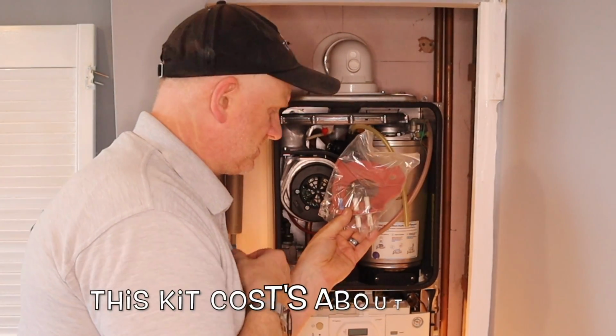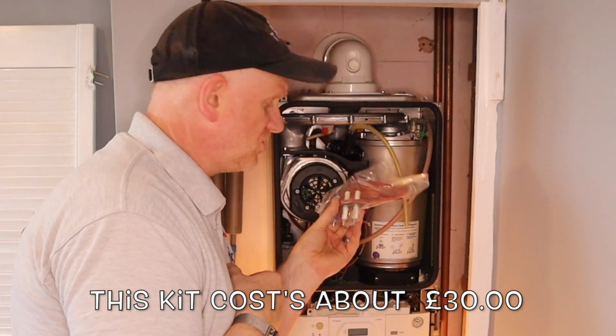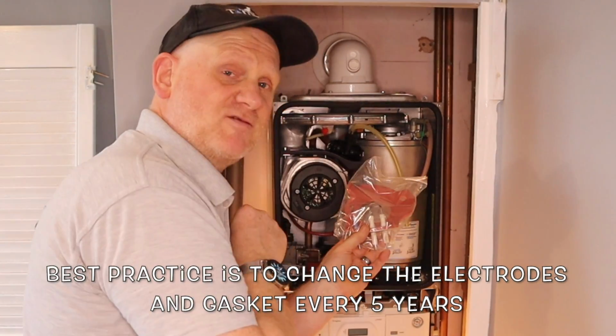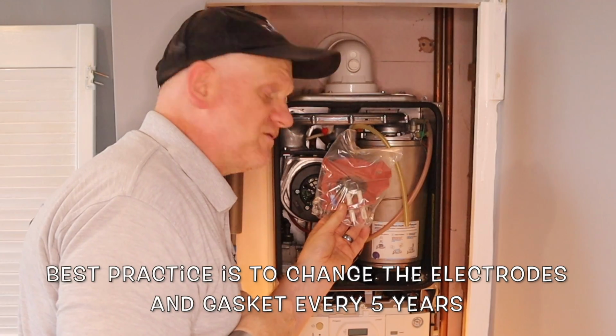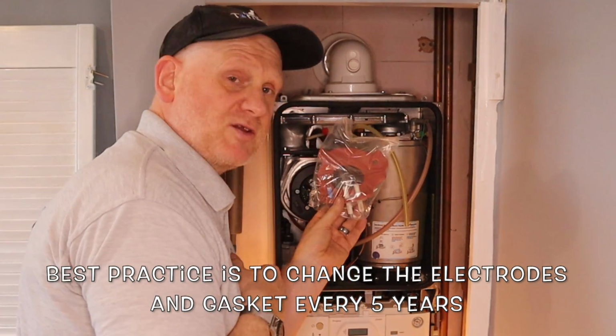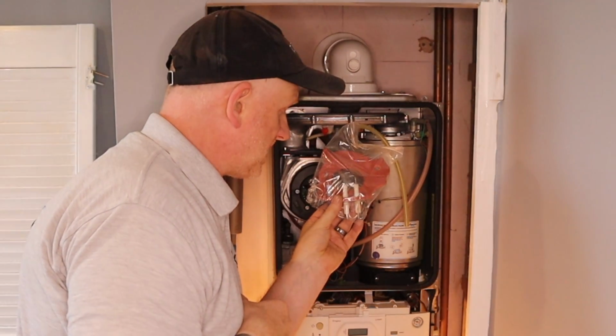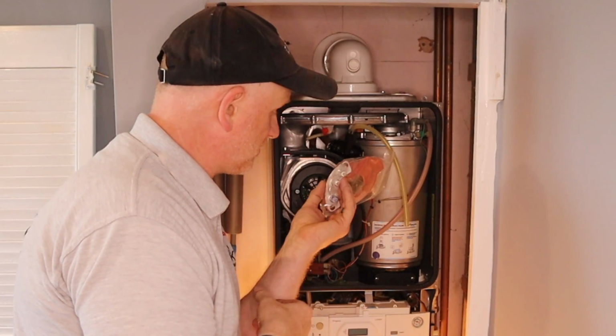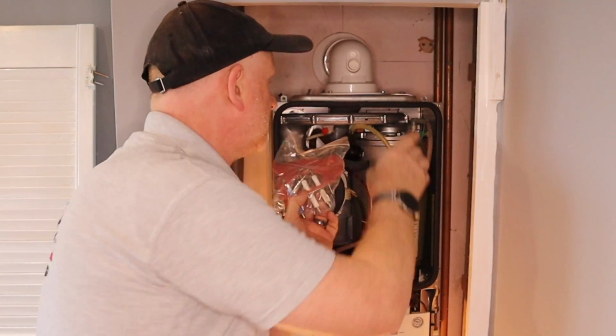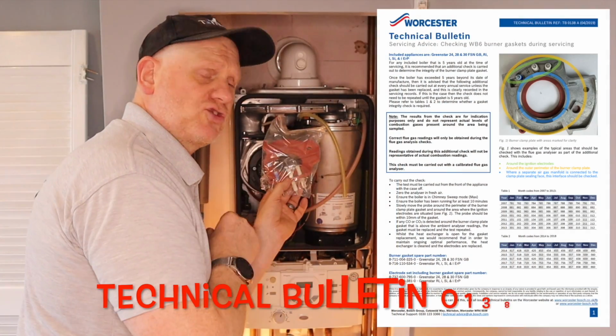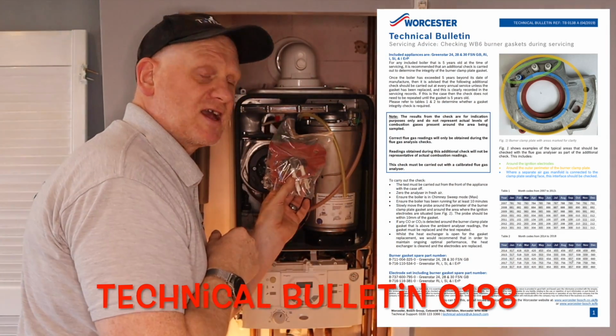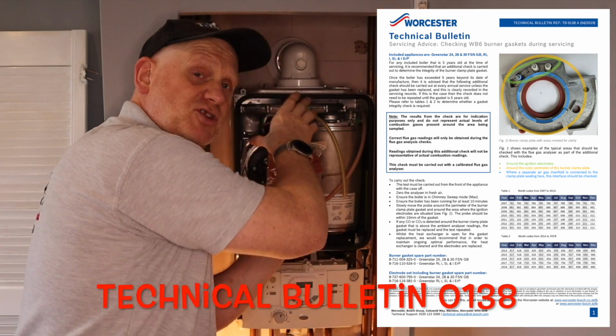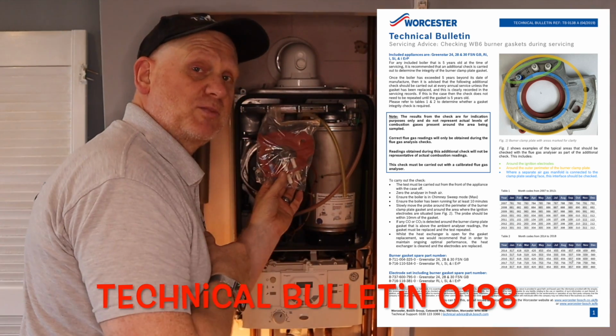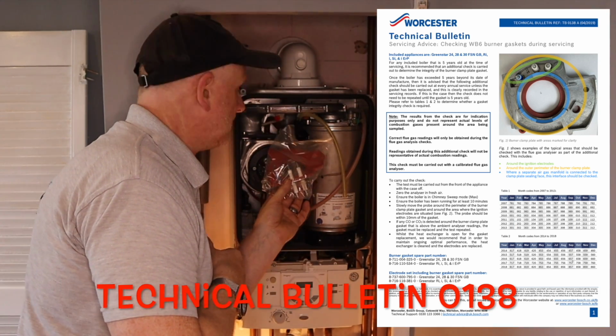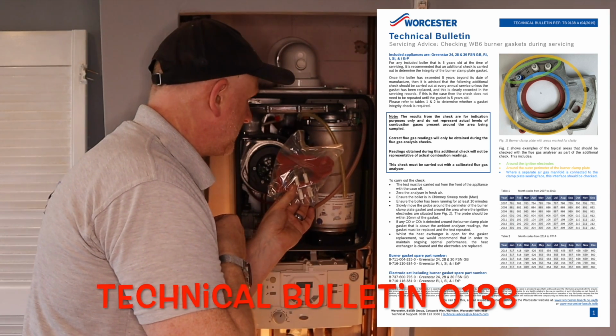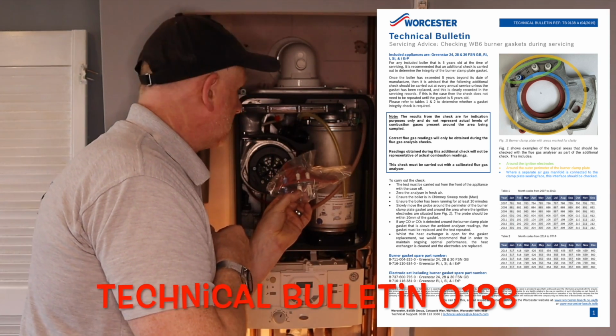Now, before you go ahead and remove this heat engine out of this boiler, you're going to require a service kit. And these are the two main components you need when servicing this boiler and removing the burner. So it's this big red gasket, and I've also bought the spark electrodes and flame rectification, which comes as one kit. So this comes as a full kit to replace that, because Worcester issued a technical bulletin about this gasket leaking. So every time you do take this heat engine out, you will need to replace this red gasket. So just need to let the boiler cool down a bit now before I take the heat engine out. So it's time for a brew.